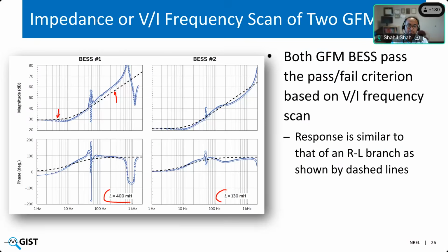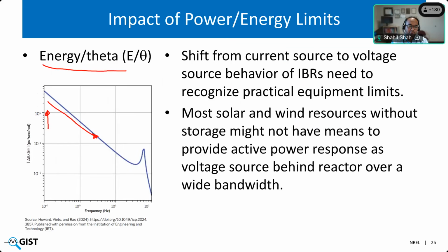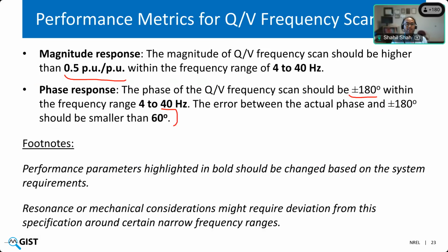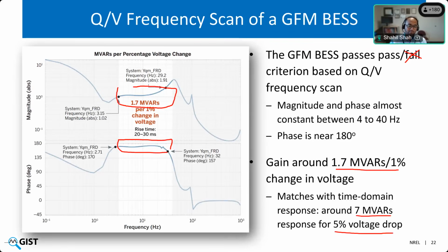Let me answer that question for maybe this Q by V scan. When you look at the frequency on the x-axis, that is really the frequency of perturbation we are injecting in the input variable, which is voltage in this case. It comes in the denominator. Basically, we modulate the magnitude of voltage at the POI of a grid forming resource at that particular frequency, and then we look for a response in the reactive power output at that same frequency.